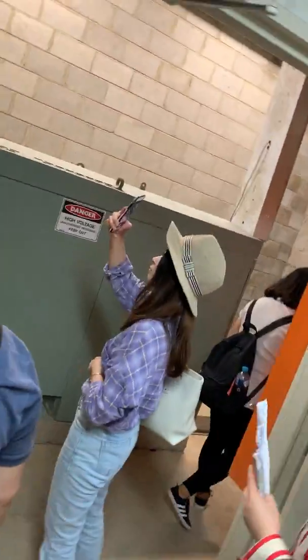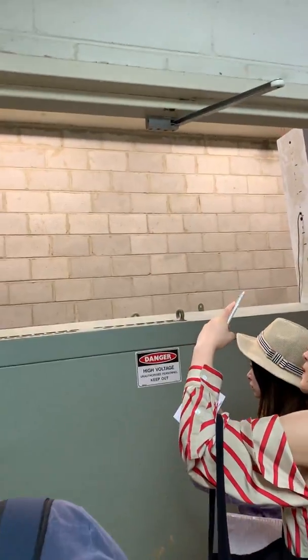I'll turn the light on so we can see it. Okay. Door jam is not allowed. These doors are self-closing doors. You can't pop them open. Part of the fire rating.